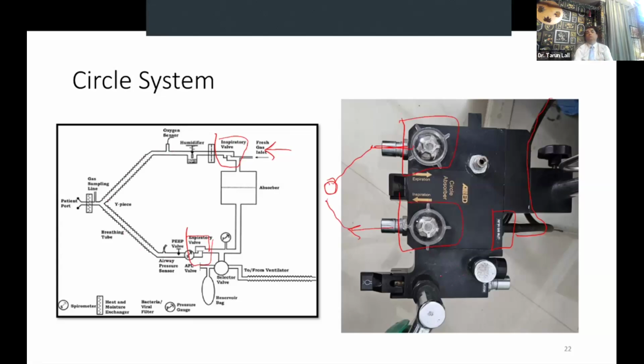Beyond which we have the selector switch. In this machine, the selector switch is on this side. Beyond the selector switch, we will have the bag. You can see that green thing hanging there is the bag. And on the other side is the ventilator. So this is the connection for the ventilator. So exactly as it is given in the book, we have it in our machine. And this carbon dioxide absorber is what would be under this. So under this console, you have the CO2 absorber.